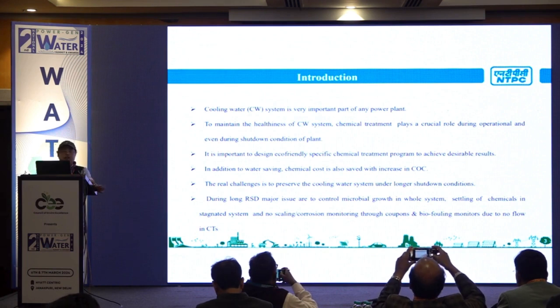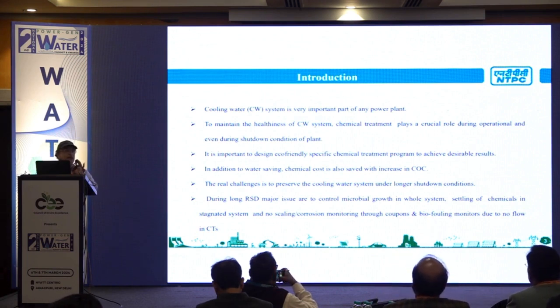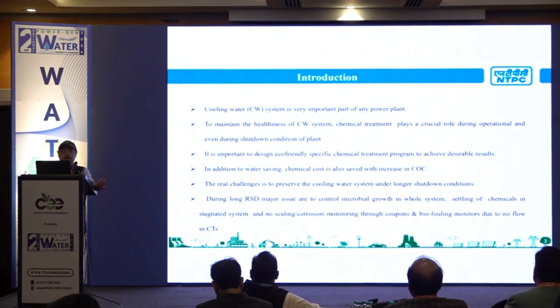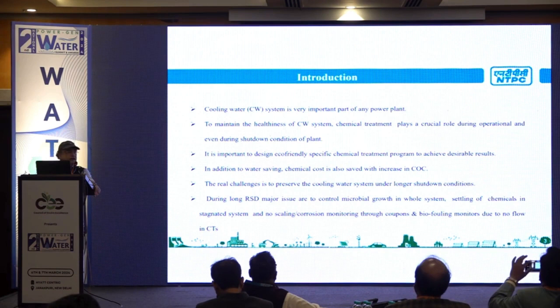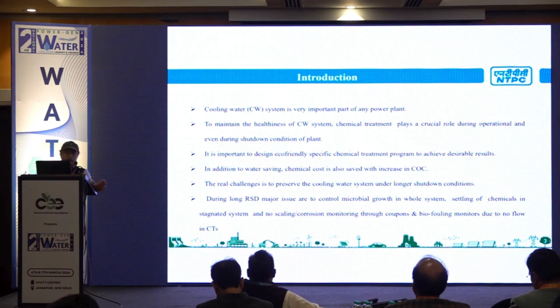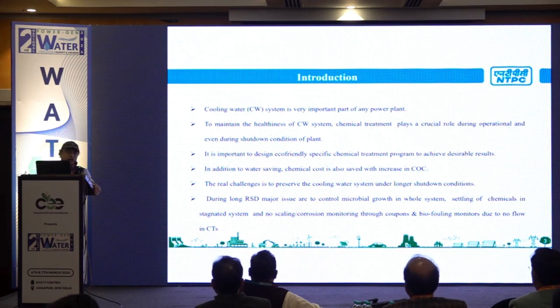This is all known, cooling water is very essential, very important for the power plant. Just to condense the low grade steam. To maintain the healthiness of the CW system, to optimize between the higher COC and possibility of the scaling or corrosion, we have to have a very selective chemical treatment. With increase in COC, there is always a possibility of decrease in the cost that I will describe later.